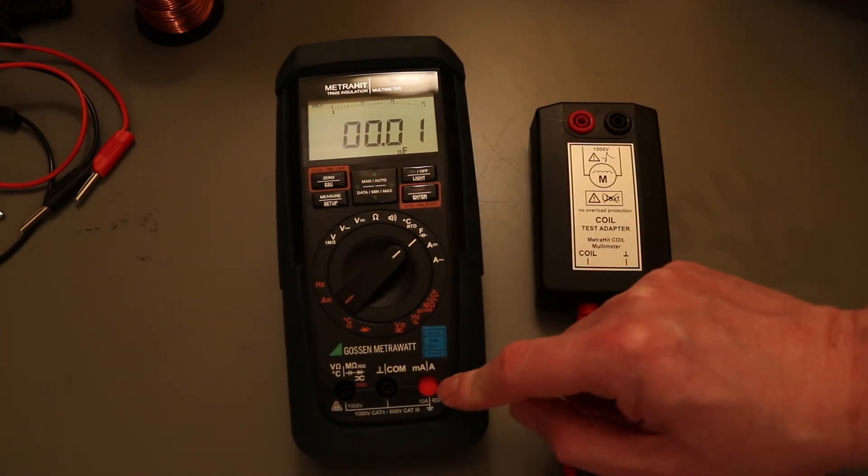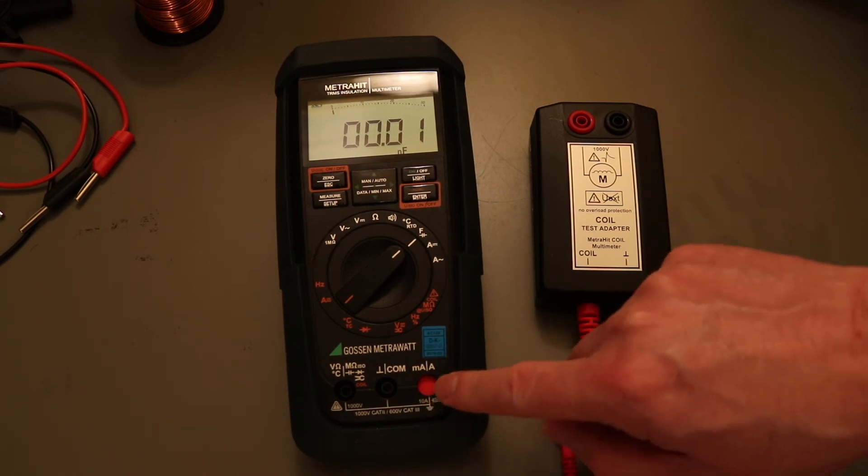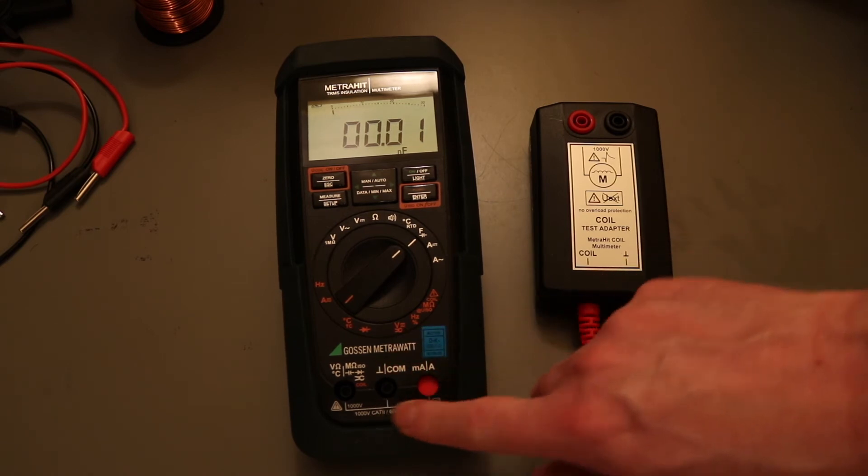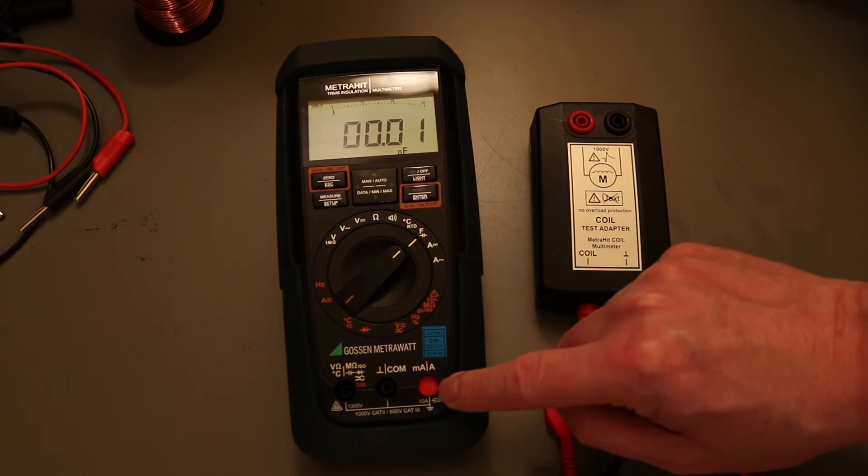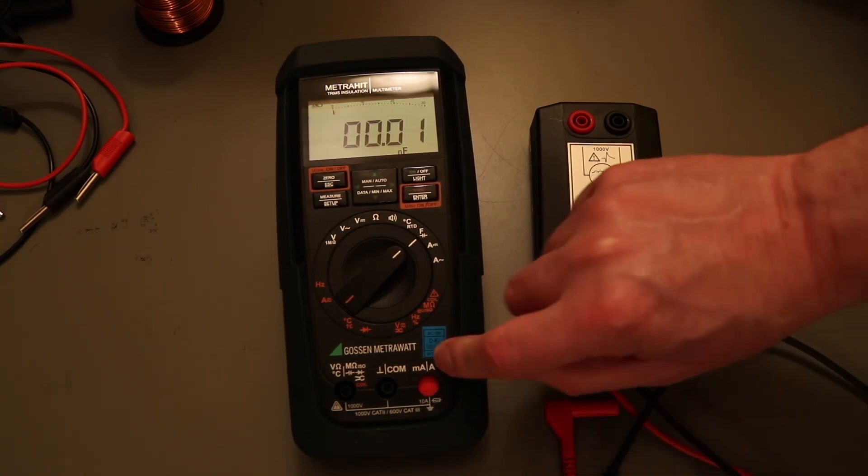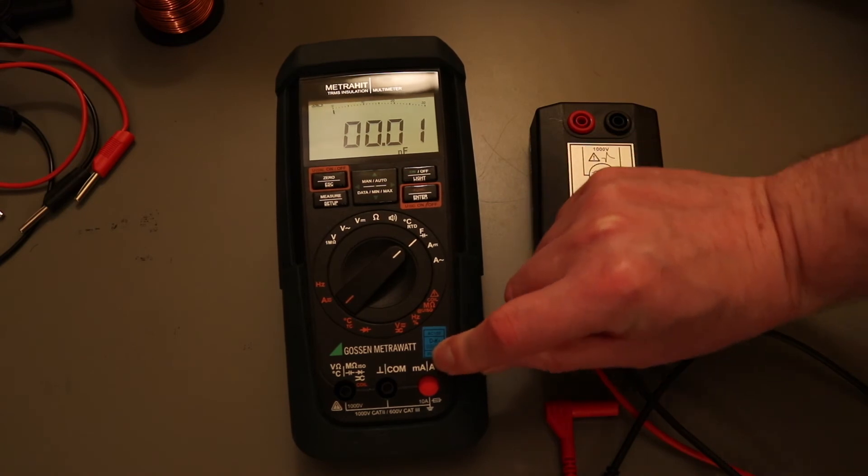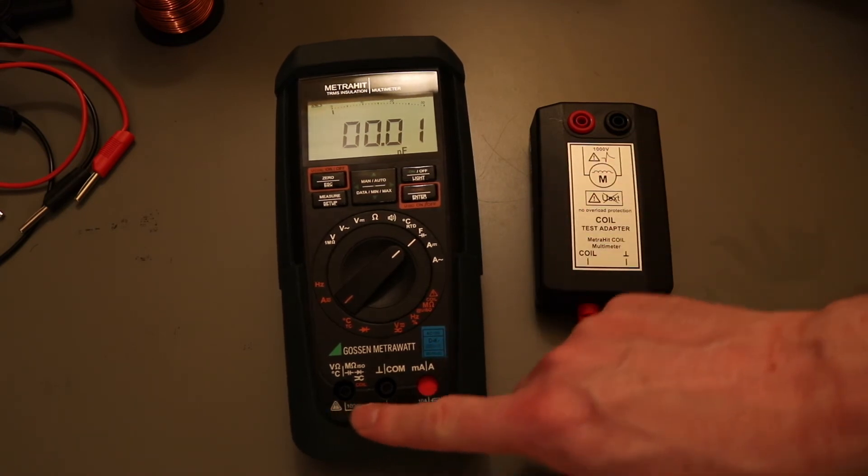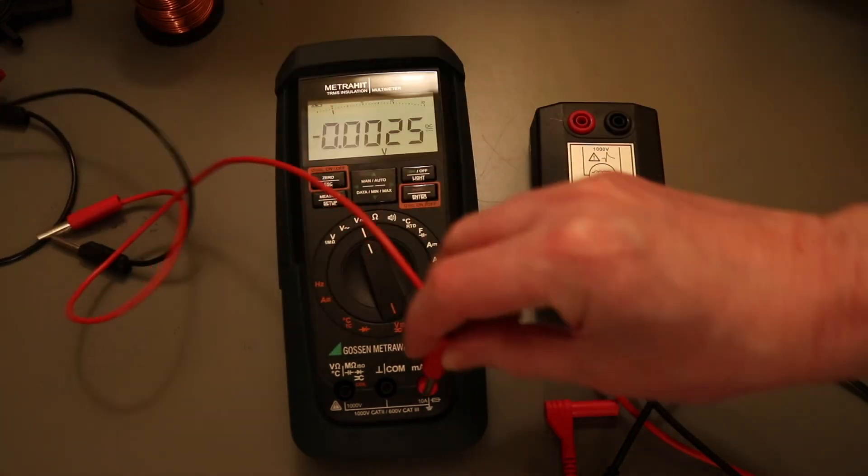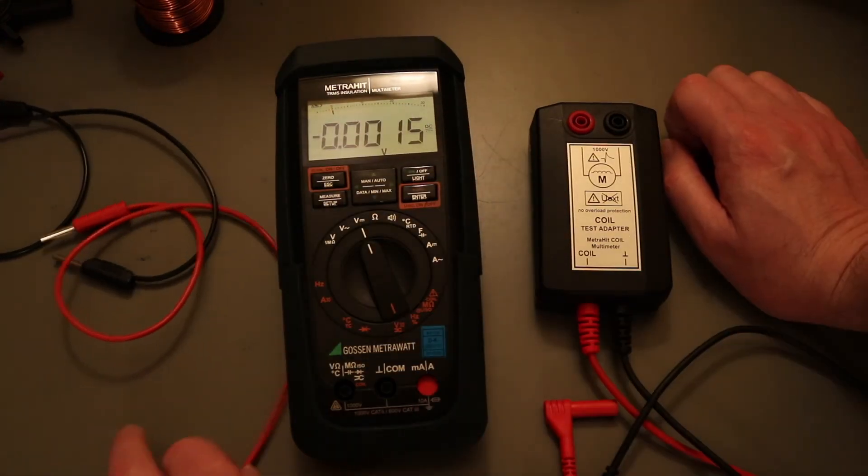Now this MetraHit range does also include Gossen's safety feature. I've only ever really seen this on Gossen MetraWatt instruments. They actually have a blank on milliamp amp function when you're on any of the voltage ones. You can see it stays there. And I can't actually physically get a probe in to that jack.